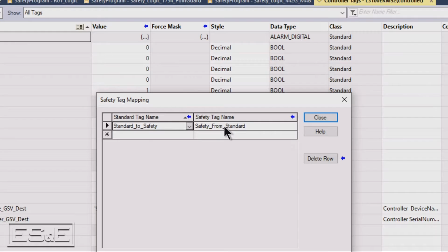It's a bit like when you did PLC-5s and SLC 500s. You had synchronous I/O updates with the program. With the introduction of Logix, it was asynchronous, so inputs could go on and off whenever through the program scan. Well, with a safety task, you don't want that to happen. You want to freeze the inputs, make it synchronous, at the beginning of the program scan. You do your logic, make a decision, and then decide what to do with the outputs.